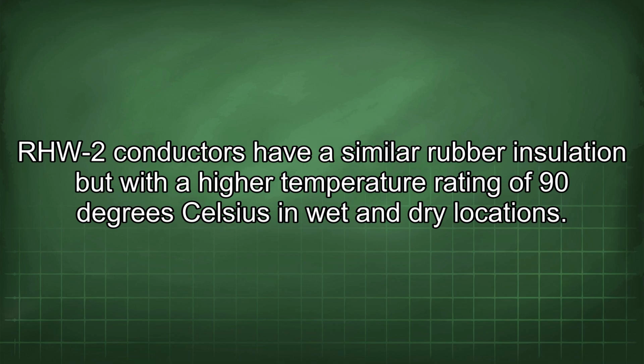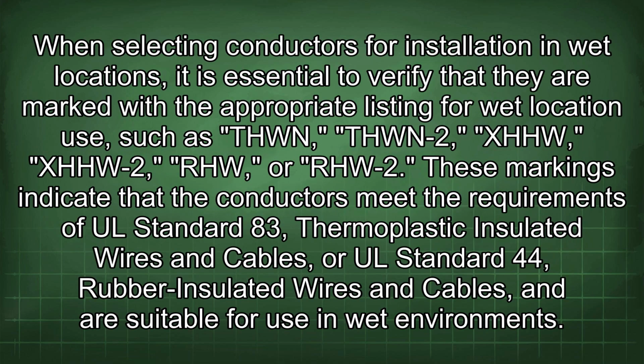When selecting conductors for installation in wet locations, it is essential to verify that they are marked with the appropriate listing for wet location use, such as THWN, THWN-2, XHHW, XHHW-2, RHW, or RHW-2. These markings indicate that the conductors meet the requirements of UL Standard 83, thermoplastic insulated wires and cables, or UL Standard 44, rubber insulated wires and cables, and are suitable for use in wet environments.